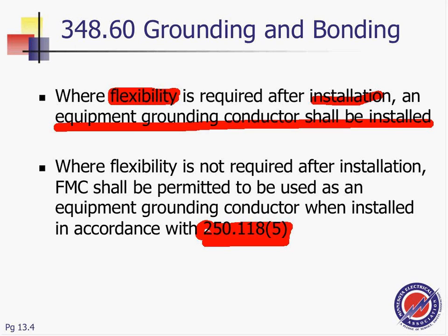So the equipment grounding conductor, if you guys look at number 5, 250.118(5), flexible metal conduit meeting all of the following. Number 1, you have to have listed fittings, not any fittings. Number 2, the overcurrent protection device can be 20 amps or less. Number 3, the length cannot be more than 6 feet. Number 4, we use it to connect the equipment where flexibility is necessary, and an equipment grounding conductor must be installed. So all these conditions are met. When all are met, then you can use the flex as an equipment grounding conductor.